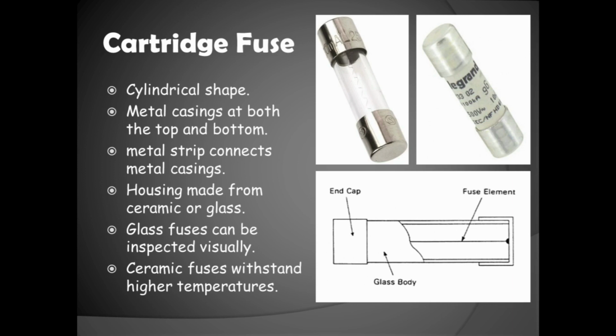In the case of DC and high voltage cartridge fuses, their cylinders are typically filled with sand or oil. This unique feature serves the critical purpose of extinguishing the arc that forms inside the fuse when it blows, effectively preventing any further damage. However, such arc extinguishing measures are unnecessary in low voltage AC applications.